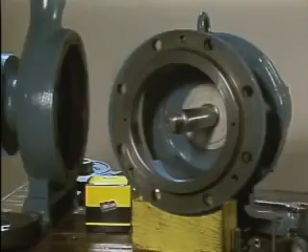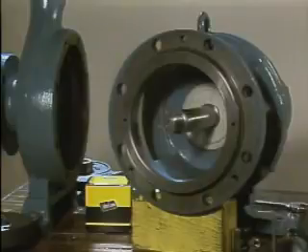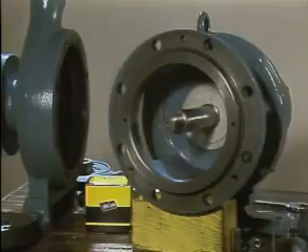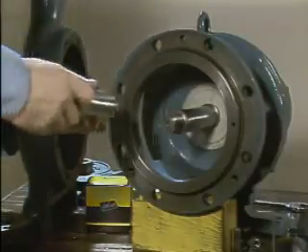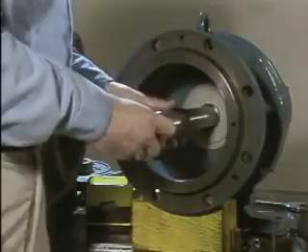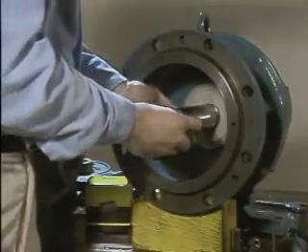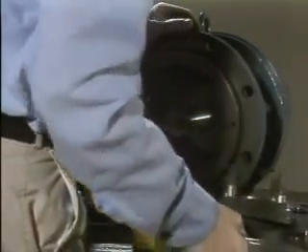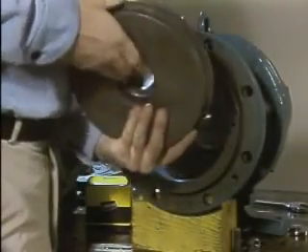Impeller clearance is usually one of the first measurements that should be taken. In our example, the rotating element of the mechanical seal mounts on a shaft sleeve. To begin reassembling components so that the measurement can be taken, the sleeve must be positioned onto the shaft. Care is taken to make sure that the sleeve is properly engaged on the drive pins or keys. An improperly positioned sleeve could be damaged when the impeller is installed.